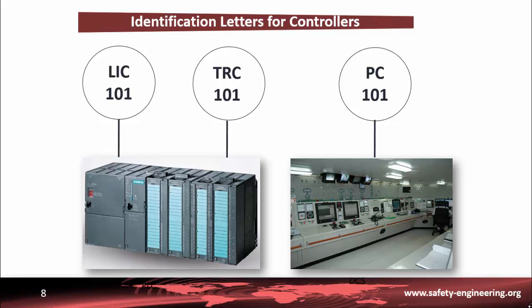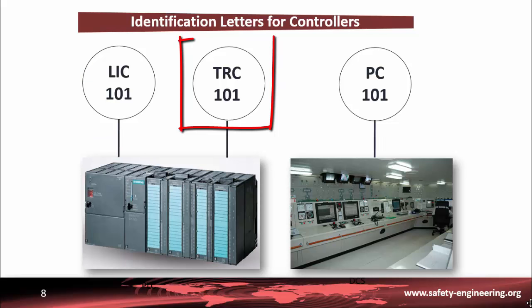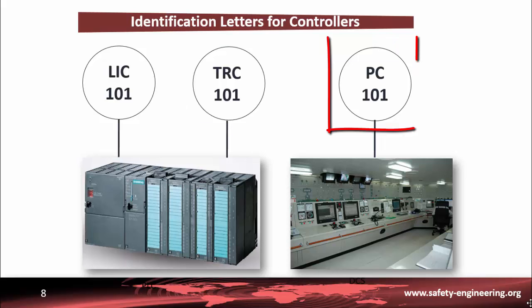Some examples are given in these slides. LIC means a controller to control the level, with a built-in indicator. TRC means a controller to control temperature, with the ability to record data such as temperature over time. PC is simply a controller to control pressure.